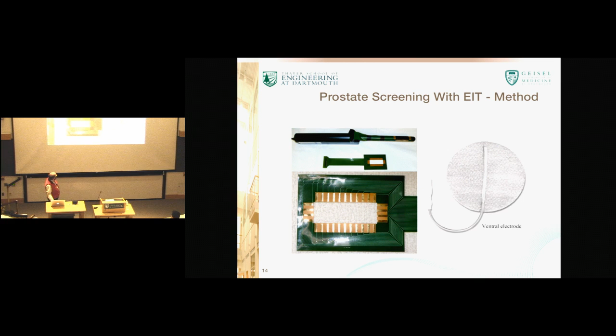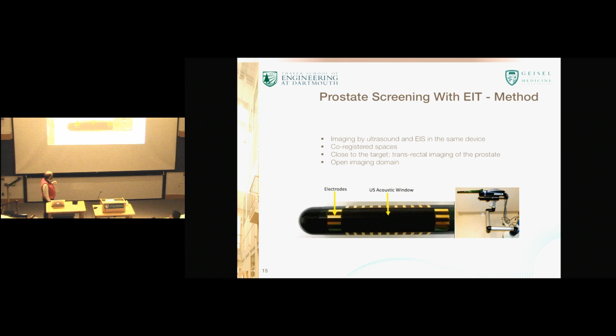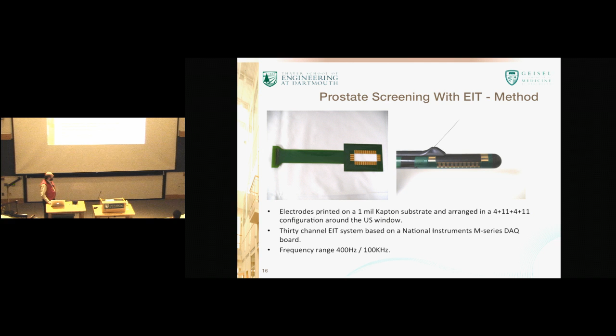This here is the same electrode array, but now mounted on the imaging probe, and you can see that we have 30 electrodes around the acoustic window. And a further view, this is a view of the same device with a biopsy needle probe. Not an enjoyable sight for some people. In any case, our device operates in the range of 400 hertz to 100 kilohertz. And we take, I believe it's 5 frequencies in that range. Yu-Ching, can you remind me? 4 frequencies for the patient data protection. Okay, 4. And it works at 9 frequencies. Okay.